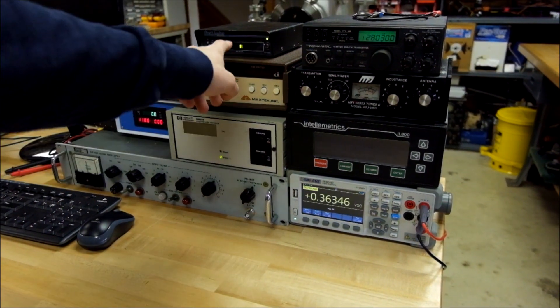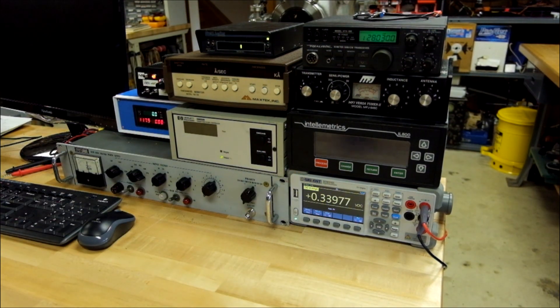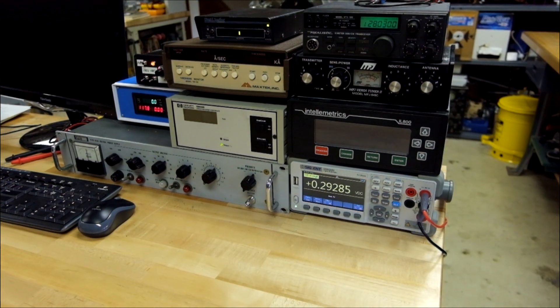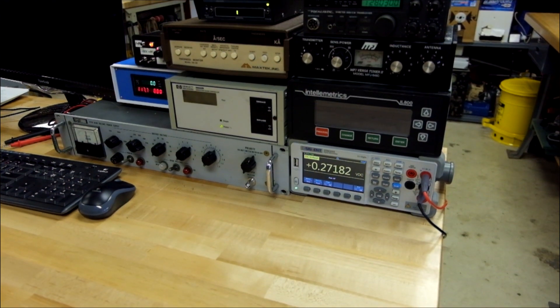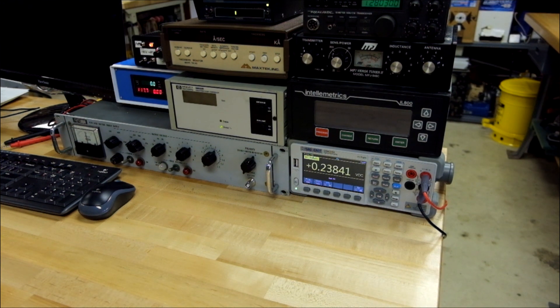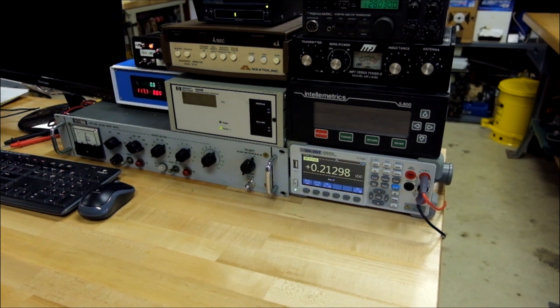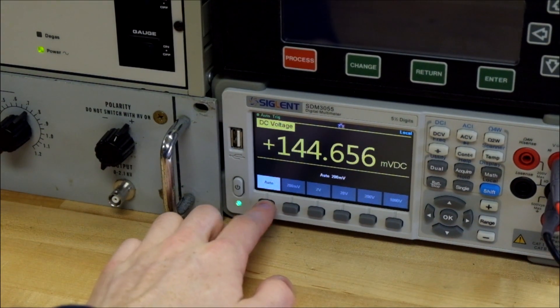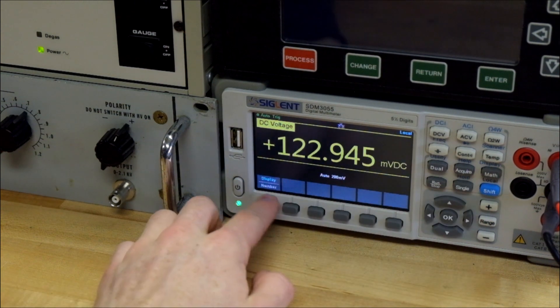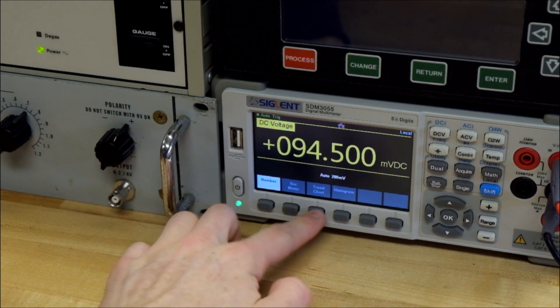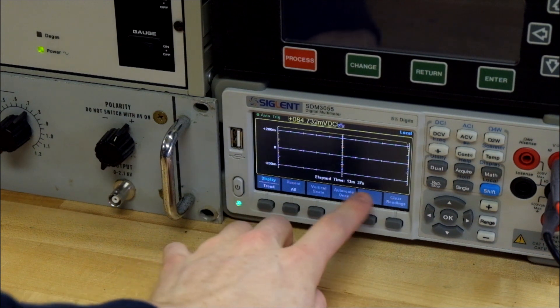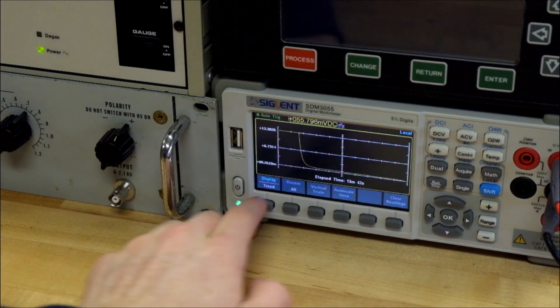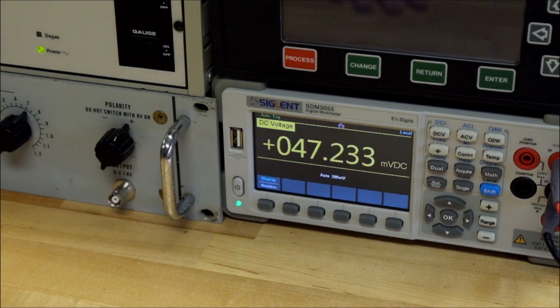The thermocouple gauge is a little bit out of spec with the pressure transducer, but I trust the readings we're getting from here. Alright, now the blades are probably about halfway, no, less than halfway spun up. It's dropping a lot, 26 millitorr, and approaching 20 millitorr. 18 millitorr, so you can get a graph of this. You'll see that it's almost like it's approaching a limit here. We've been pumping for 13 minutes, so you'll see that was the action in the mechanical pump, and this is the turbo is doing the last little bit here.